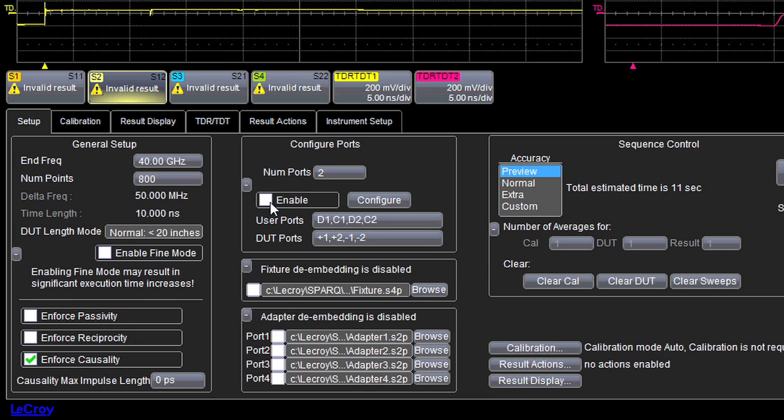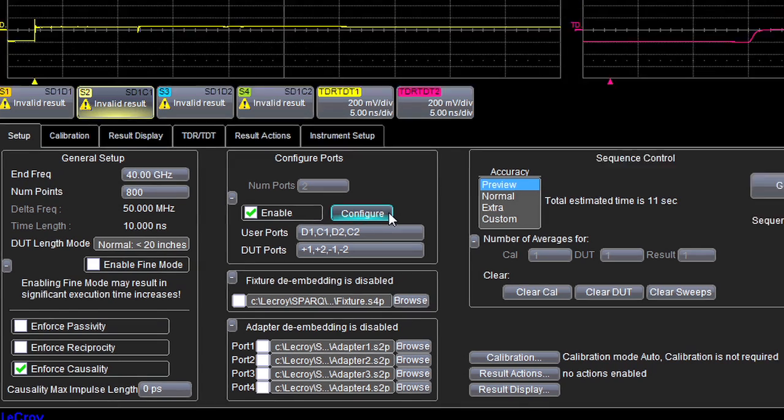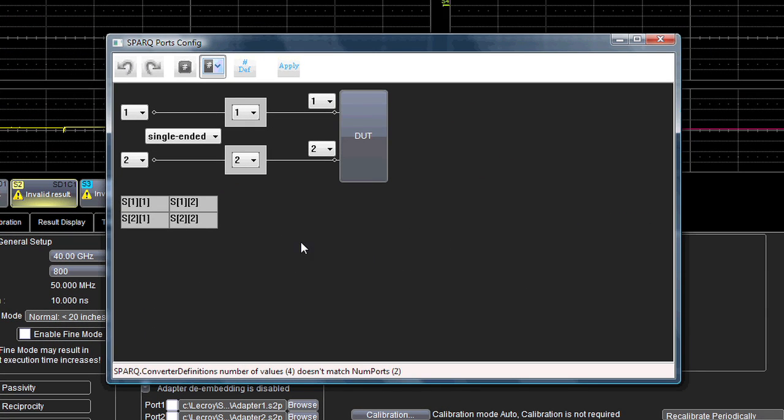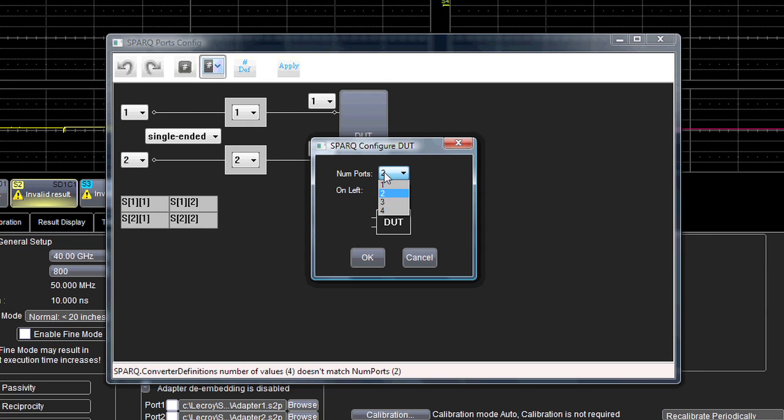Since our DUT is designed to carry a differential pair, we'll want to use the differential and mixed-mode S parameters to gain more insight about the backplane's ability to transmit differential signals. To do this, we go to the advanced screen that lets us set up the port configuration.